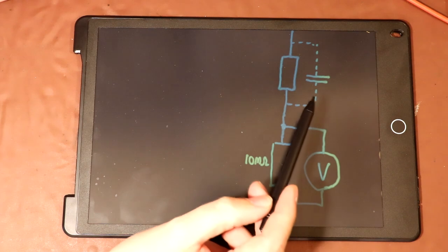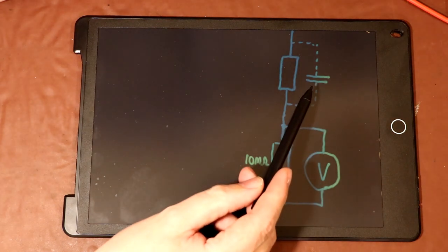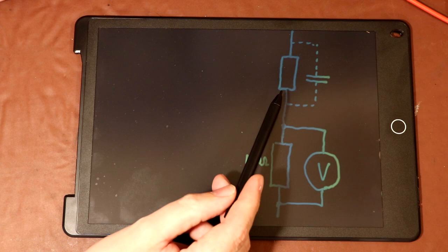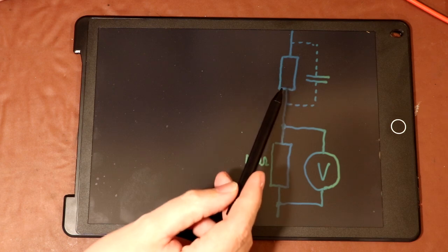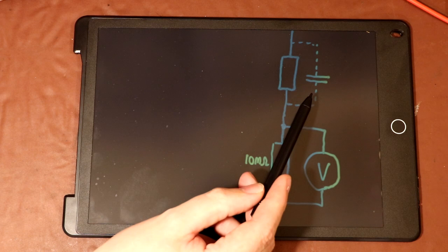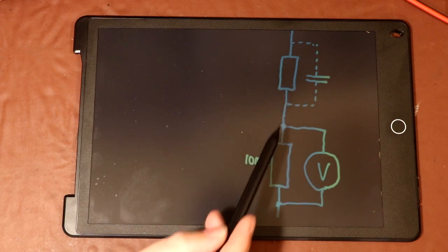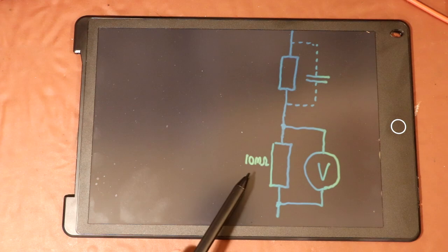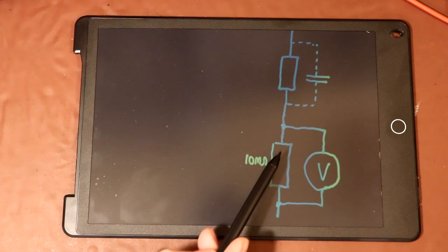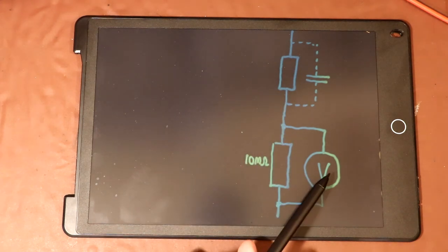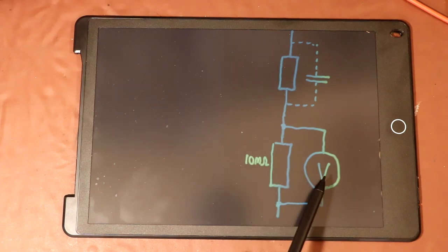So we've seen the mechanisms now, where stray capacitance in an AC circuit or resistance within a DC circuit, but of course you can also get moisture and resistance in an AC circuit as well. But those resistances actually form a potential divider with the very high input impedance of the voltmeter, and even though we have really tiny currents flowing into our voltmeter, the voltage indication can still be much higher than we would expect. They call these misleading measurements phantom or ghost indications because they aren't indicative of the true voltage flowing in the circuit.